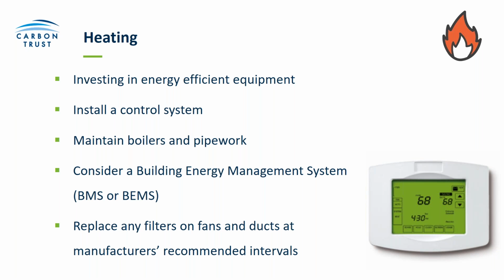So just a little recap on heating and some of the things that you can look at. Investing in energy efficient equipment. So if you do have really old and inefficient heating systems, it's worth having a look at replacing those. But before replacing them, as we mentioned further down, have a look at the boilers and pipework that you have. Make sure that it's properly maintained and being insulated as well. So if you're walking into your boiler room, for example, and you can feel that it's warm in the room, that means that a lot of heat has been wasted. It's not going where it should do. So that could benefit from some insulation. Control systems as well, and so making sure that you have things like that dead band period.